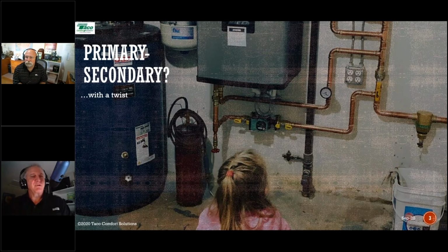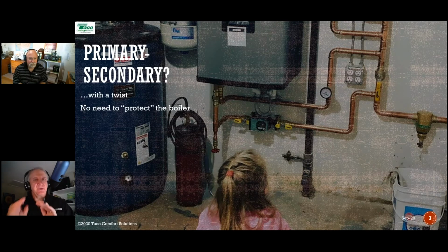That's with a cast iron boiler, and that's done with an eye towards protecting the boiler from low return water temperatures that would create flue gas condensation. We don't want that with a cast iron boiler, but we do want that with a ModCon boiler. We don't want to protect the boiler in any way, shape, or form. We want the lowest possible water temperatures going back to that boiler. The more we abuse that boiler with low return water temperatures, the more it rewards us with efficiency.